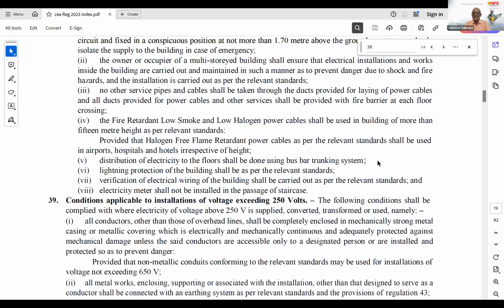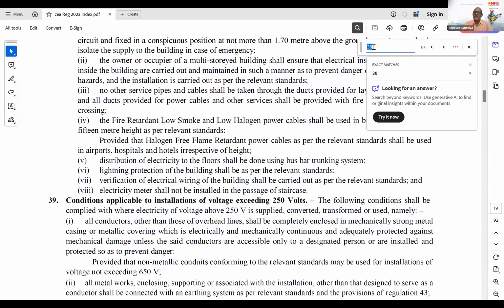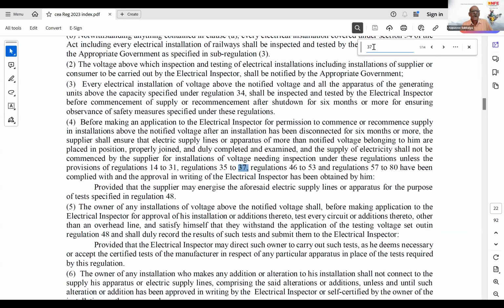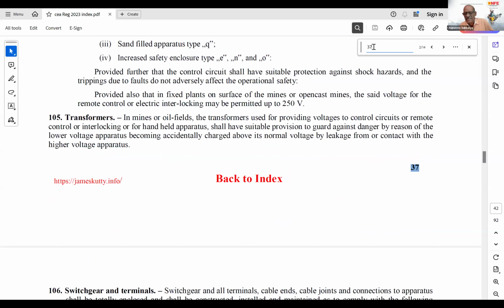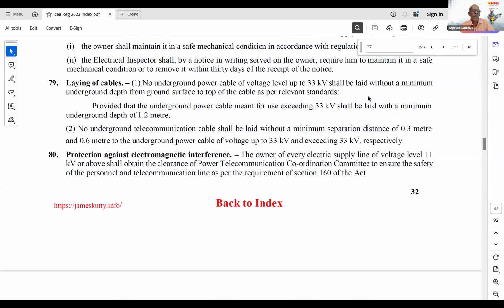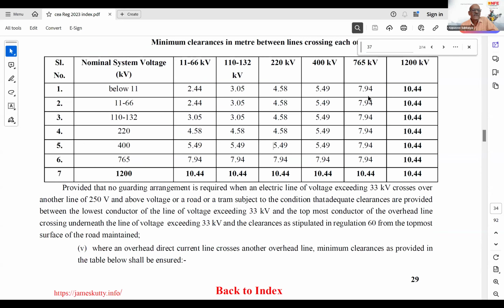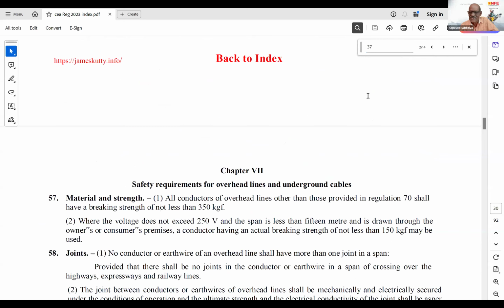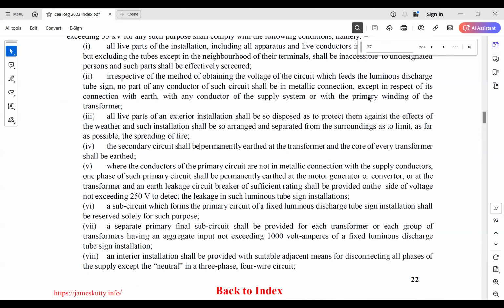I think the Central Electricity Authority regulation has also insisted on breakers at the point of supply, irrespective of the capacity. Could you throw some light on this specific regulation, which requires all the consumer premises who are availing 11 kV and above supply to provide a breaker? Could you please throw some light on this, and what are all the issues or advantages, sir? I will just go to this regulation slide. Yes. 37 or 38? Yes, regulation number 37, clauses number 2 and 3.